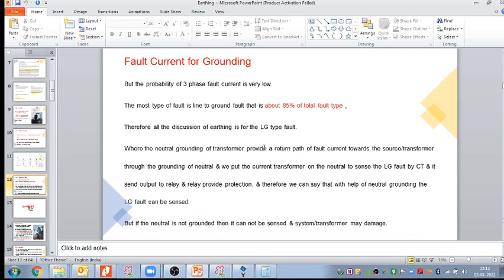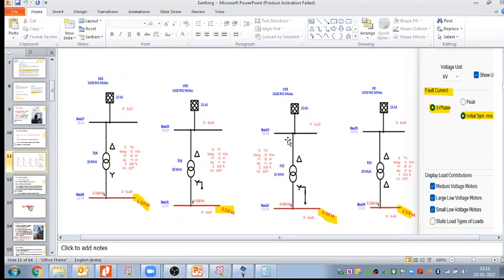Next, please. Sir, the story behind this is, as you concluded, that in case of a three-phase fault there is no need of grounding in order to protect the system. It's not mandatory for three-phase only, right? And for other cases, like unbalanced cases, there is a must to apply some grounding, be it neutral grounding resistor or solid grounding. The story, I guess, is that in case of three phase the system is symmetric. We draw only the positive sequence circuit. The neutral voltage is zero, and it remains zero in case of a balanced three phase fault. But on the contrary, in case of an unbalanced fault there is a neutral voltage, and that neutral voltage leads to current. That is why neutral grounding in case of an unbalanced system is mandatory. Am I right? Yeah, you are correct. You are 100% correct.